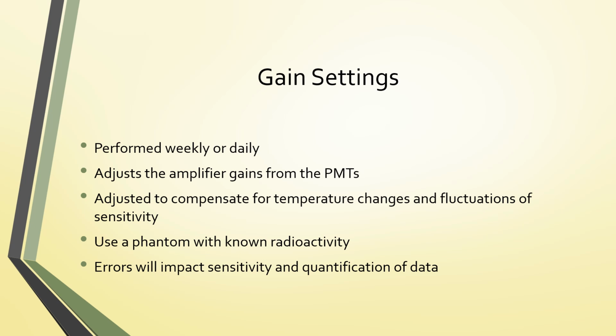The gain settings are performed weekly or daily. This adjusts the amplifier gains from the PM tubes, and this is adjusted to compensate for temperature changes and fluctuations in sensitivity. For this one, we use a phantom with a known radioactivity, and then errors will impact the sensitivity and quantification of the data.